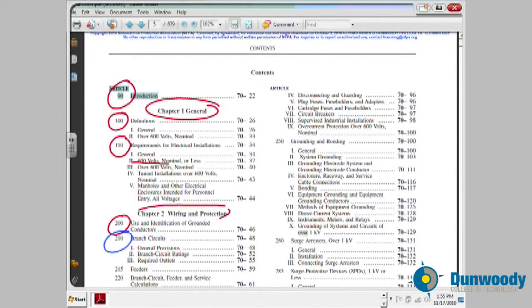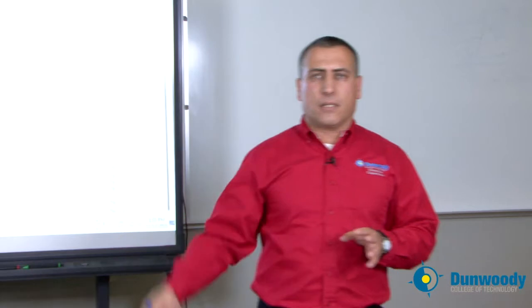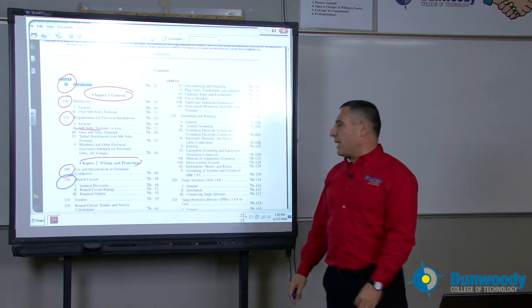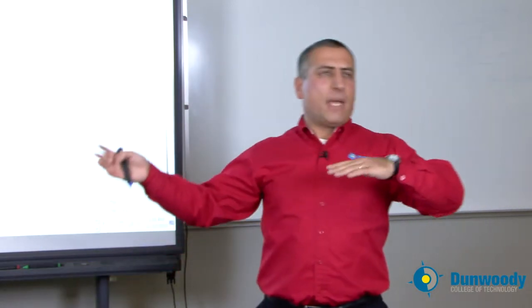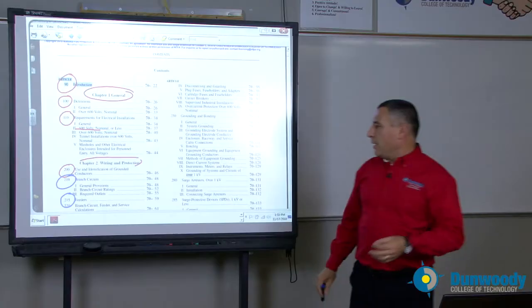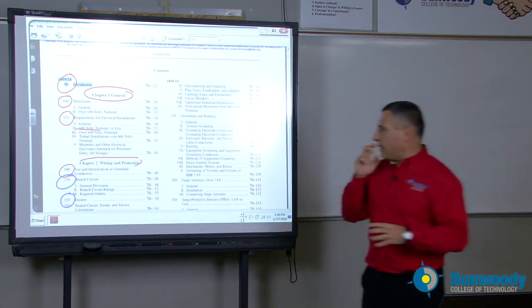Then we move into branch circuits, which are extremely important — lighting branch circuits, receptacle branch circuits, dedicated circuits. What is the largest branch circuit I can pull out of a panel? All this information is in Article 210. Feeders are covered in Article 215. Feeders are conductors and conduits between two panels — for example, bringing from a 4,000-amp panel into a 2,000-amp panel. How do you size and protect a feeder with an overcurrent protection device? Branch circuits and feeders are extremely important topics.